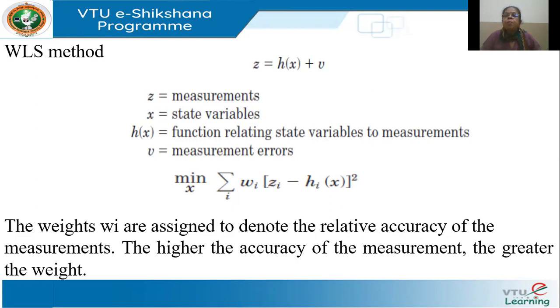So what is my optimization problem? See, Z is the parameter I have actually measured. X is the total number of variables, system state variables. Z will be less than X. If I measure all X, I don't need any estimation. So the number of measurements is less than the number of state variables. So I have a function H relating the state variables to the measurements. And V is some measurement error. There are ways to model the error. Random noise and all that you can model.